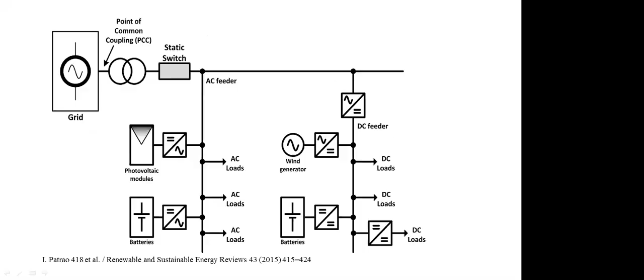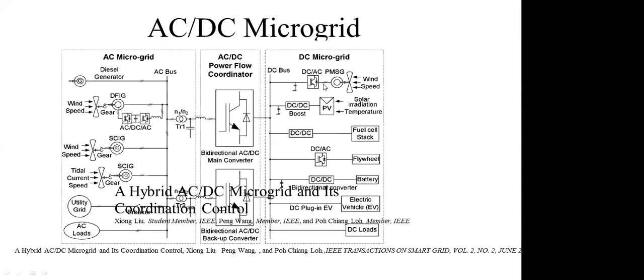This is one of the representations of an AC/DC microgrid. Here you can have different sources with different configurations, and you have a bidirectional AC/DC main converter and bidirectional AC/DC back-up converter. So you can have different sources and different configurations also in an AC to DC microgrid. That means, why do we want to put a DC microgrid here? If it is possible to use the DC power directly, you use it. That's the flexibility you can have with an AC/DC microgrid. But if you go for such a configuration, the complexity of your operation and control issues becomes more, so that also needs to be taken care of.